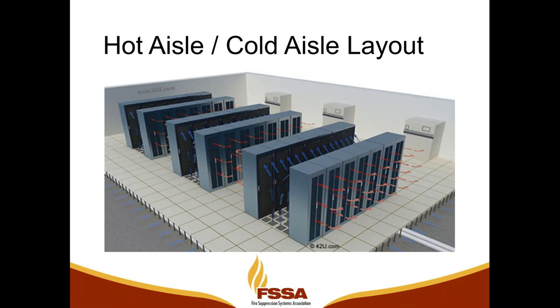And so when you look at a rack, like in this picture, there are 6 rows of data racks. There's a hot face to the data rack and a cold face to the data rack. The cold face is where we want to deliver cooling air to the computers, and the hot side of the rack is where that hot air is rejected. And so many data centers nowadays have 2 hot faces facing each other, which creates a hot aisle, and then the remaining cold faces facing each other for the cold aisle.